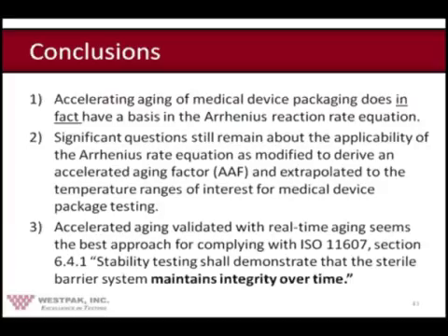Okay, at the risk of getting kind of bogged down here, let me go through some conclusions, and then we'll see if any questions remain. So at the end of this hour-long dissertation, I hope that we have shown definitively the following three items. One, that the accelerated aging formulation in this ISO 11607 does have its basis in the Arrhenius reaction rate equation. I hope we've shown you that there is a relationship between the two.